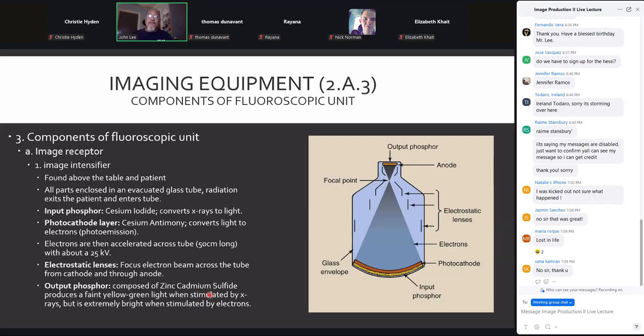So going from zinc cadmium sulfide to image intensified fluoroscopy was a huge step, because before, the radiologist was the only one that got to look, unless he pointed the mirror for you to see or got out of the way. Image intensified allowed us to attach a television camera tube to the output phosphor and generate an electronic signal that would go out to a TV monitor, so that now everybody in the room on the same side of the monitor could see the study, including the patient.